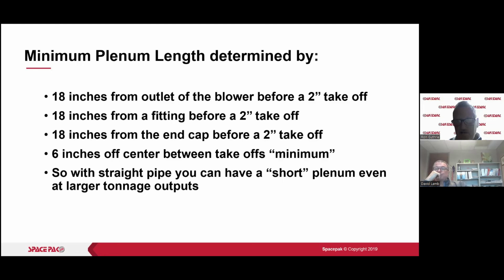6 inches offset between the takeoffs, minimum. And when you figure that you've got a 2-inch round circle on two sides of that, it's really only 4 inches between. So 6 inches on center between takeoffs is the minimum. Leave more than that, you're better off.